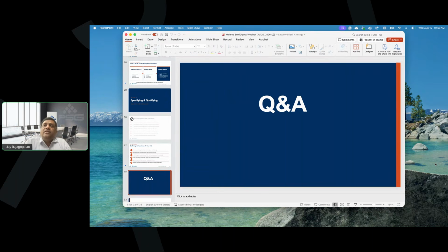And then you have to orient these sensors in such a way that bubbles are not accumulated and trapped in certain locations, thereby preventing the flow measurement from happening. So, for example, in ultrasonic flow controllers or flow meters, we use Z-shaped sensors. You can orient the Z shape at, like, a 45-degree angle, for example, thereby avoiding any trapped zones for the bubbles to accumulate.